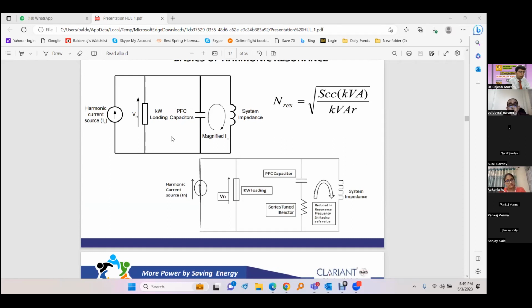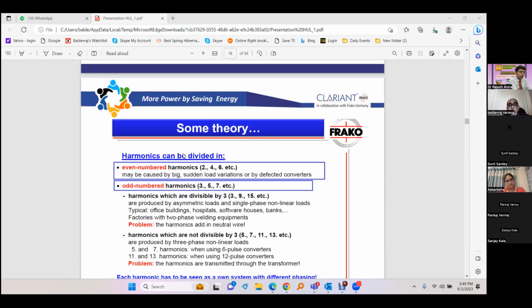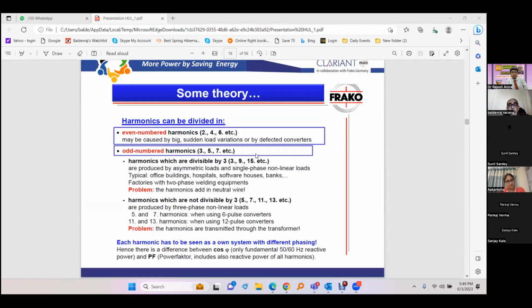So in harmonics, we have even numbers, 2nd, 4th, 6th, and odd numbers, 3rd, 5th, 7th, and so on. One is positive sequence harmonics and the other is negative sequence harmonics. Normally we get 5th and 7th harmonics because mostly our loads are 6-pulse converters, the non-linear loads. So we have these harmonics mostly, and we have to take care of these harmonics mainly. And we have a third type of harmonics, which are multiples of 3: 3rd, 9th, 15th, 18th, 21st and so on. These harmonics are called zero sequence harmonics.